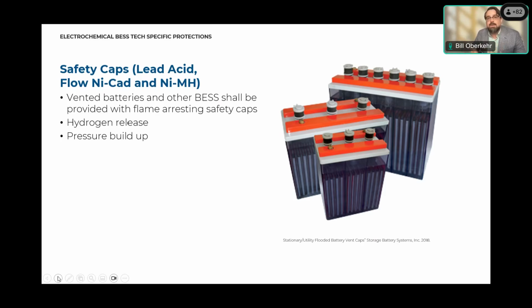We only see buildup of these gases and off-gassing in lithium ion systems as a result of a catastrophic failure. So during normal charging and discharging operations, these hazards are not presented by lithium ion batteries, and therefore they're not regulated by the code.